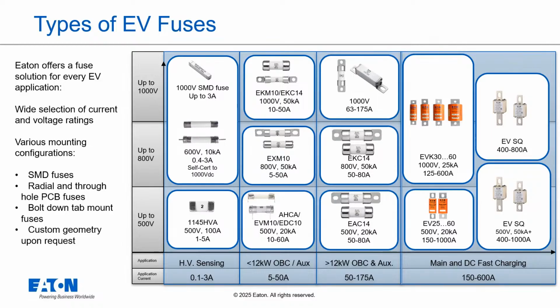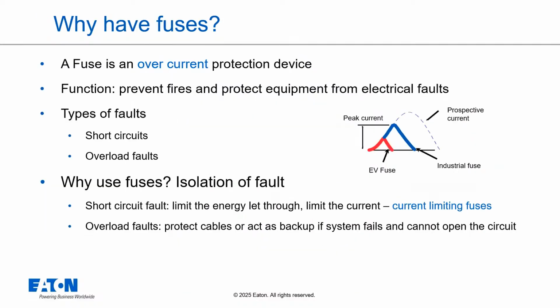Okay, simple question, but fundamental. Why do we use fuses in the first place? At its core, a fuse is an overcurrent protection device. Its main job is to prevent fires and protect expensive equipment from electrical faults. There are generally two types of faults we're concerned with: short circuits and overload faults. So why a fuse specifically? The key benefit is isolation of the fault. In a short circuit, fuses are designed to quickly limit the amount of energy let through and limit the peak current. We call those current limiting fuses.